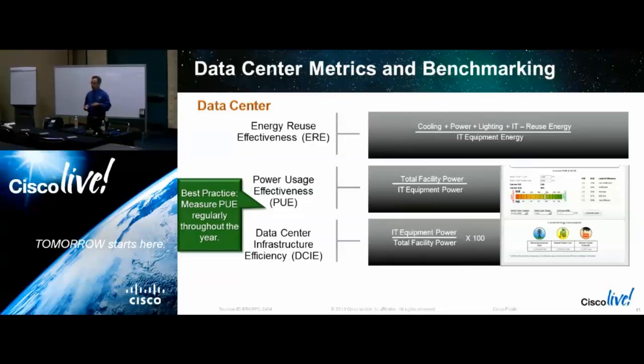And of course, no talk would be complete without PUE, and there he is. But if you're going to do PUE, do it regularly. PUE is a point in time. It's affected by a number of things, including what the weather is today, according to what the business is today. So when you do that periodically and regularly at points across the year, then you have the ability to normalize it and understand what the PUE is telling you.